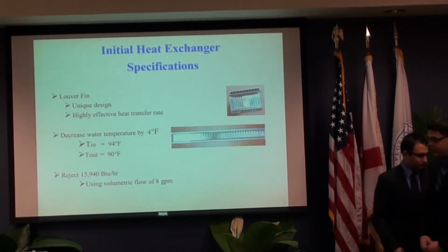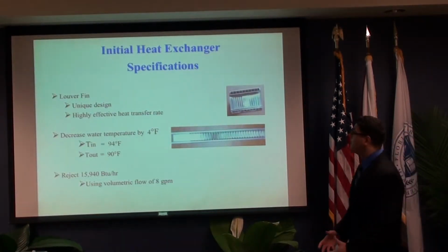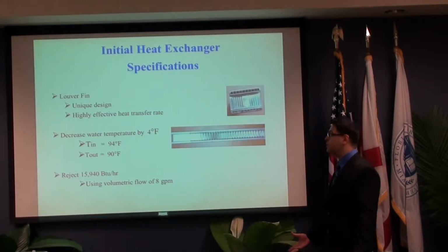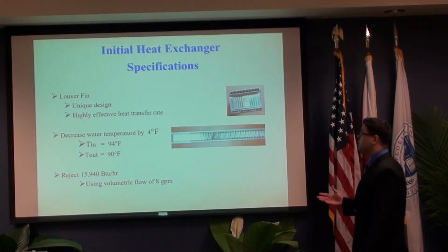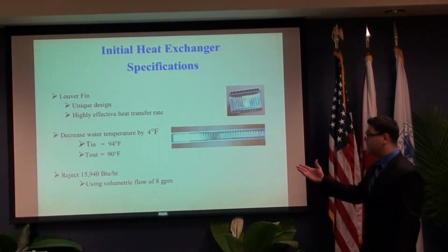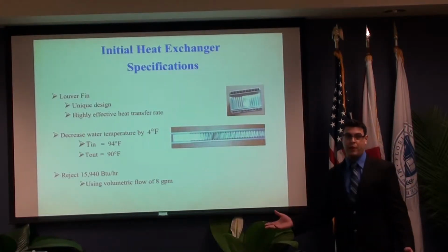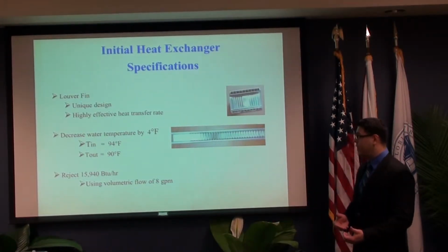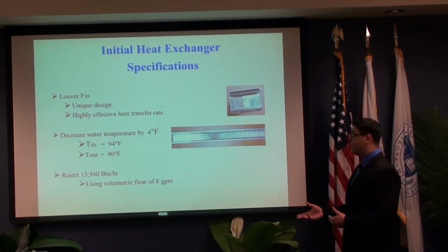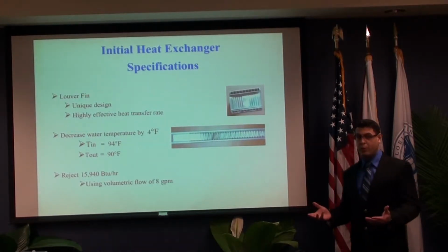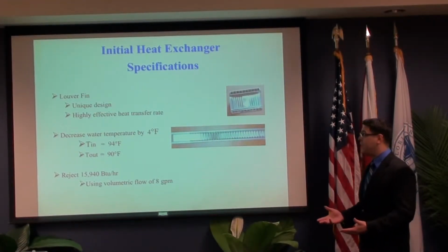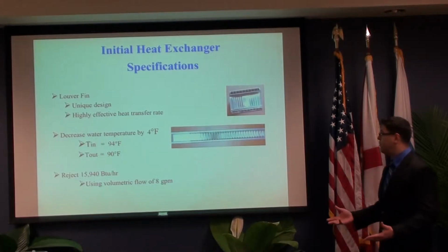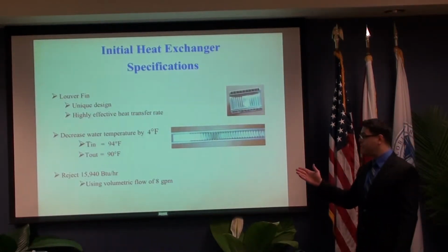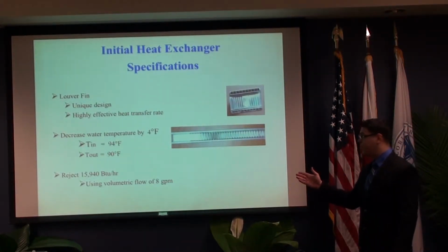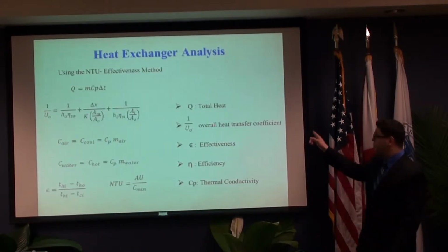So based on these specifications, we came up with an initial heat exchanger that we wanted to design. We wanted to choose a heat exchanger that was louver fin and that can decrease the water temperature by 4 degrees Fahrenheit, meaning the water was going to go in at 94 and leave at 90 degrees Fahrenheit. The reason why we chose a louver fin heat exchanger is because of its unique design and its highly effective heat transfer rate. We were also planning on rejecting 15,940 BTUs per hour and continue to keep the flow rate of 8 gallons per minute. And there are some pictures.